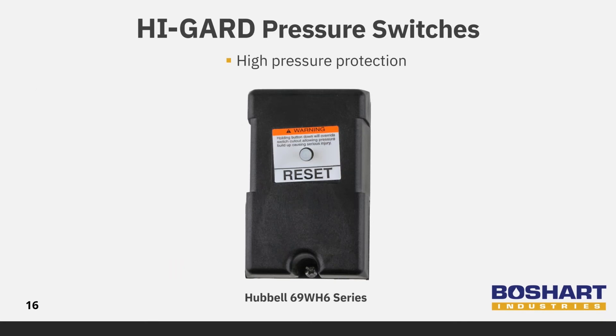Hubbell's Hi-Gard switch is also wired in series with any system pressure switch. This special pressure switch is designed to cut out when a preset pressure is reached. It must be manually reset. These pressure switches are used when it is desirable to limit the maximum pressure in a system.